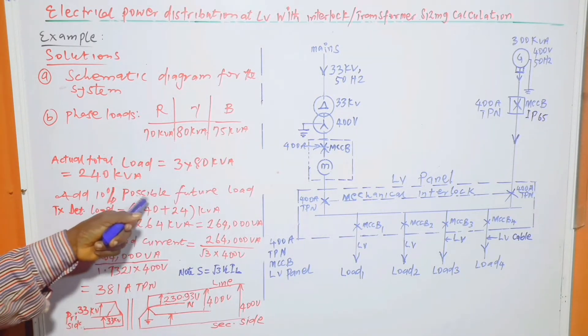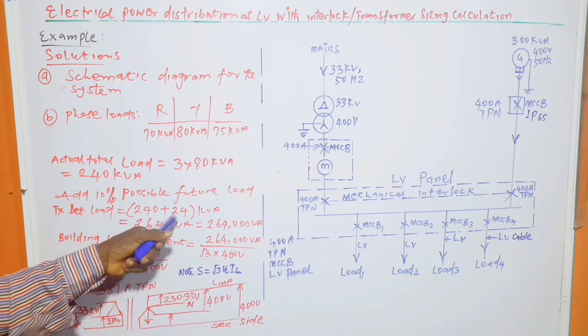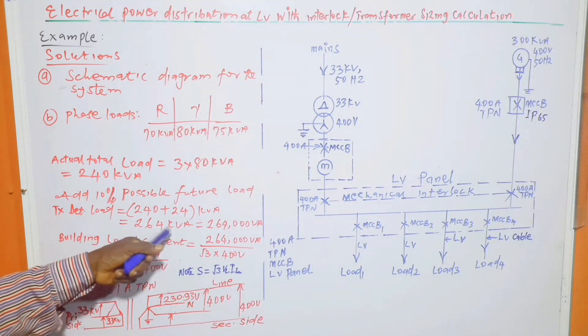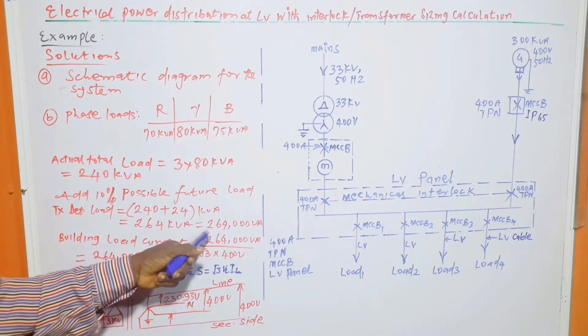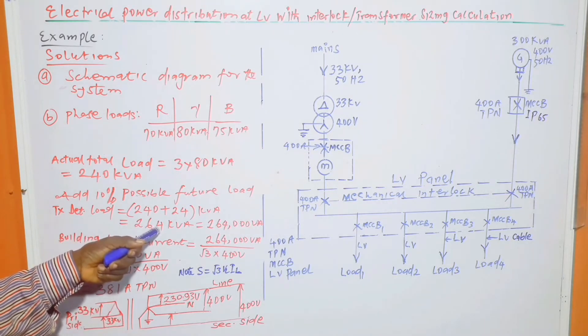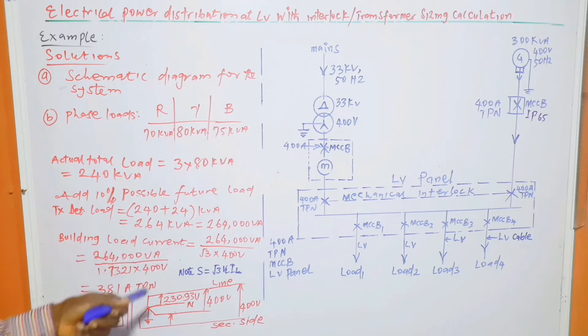Now, add 10% possible future load. Then transformer rating determining load is equal to 240 plus 24 kVA, which is equal to 264 kVA or 264,000 VA. This is the building load, 264 kVA, which is the answer to the B part.